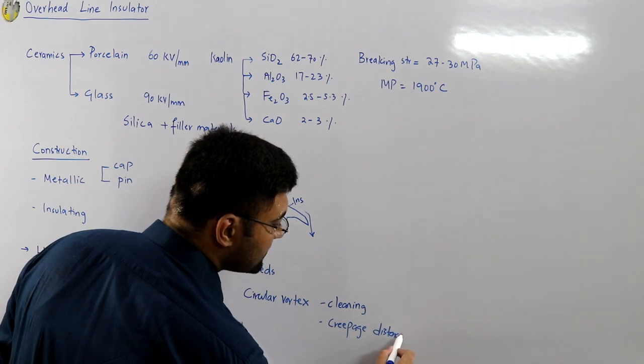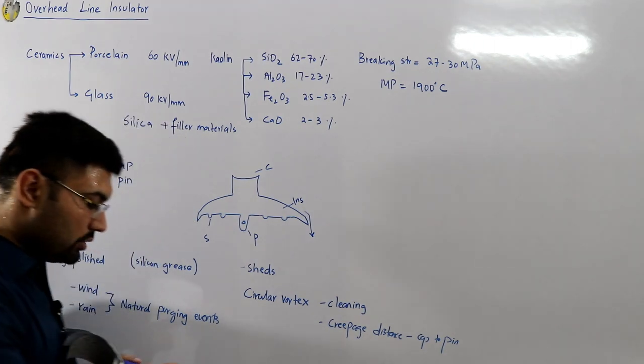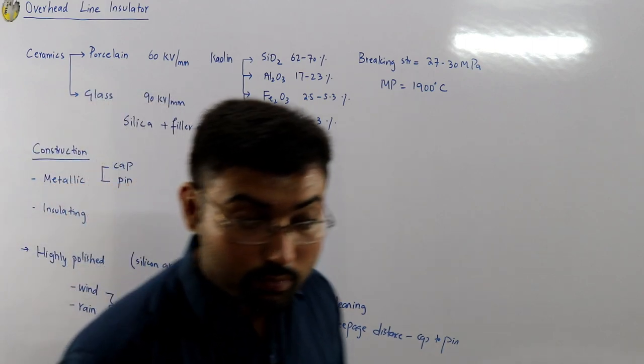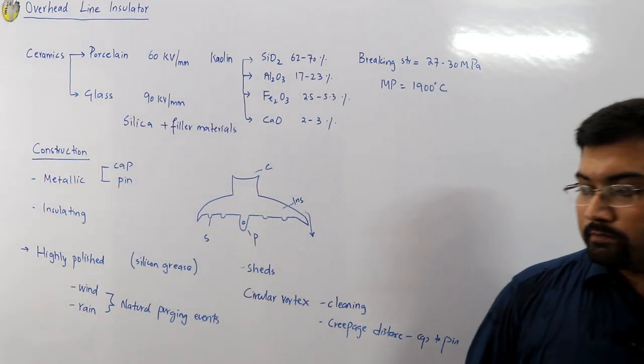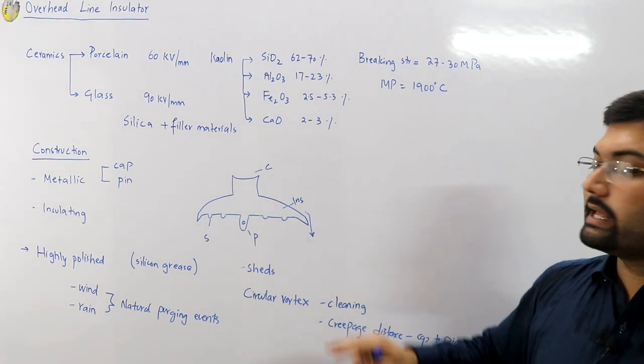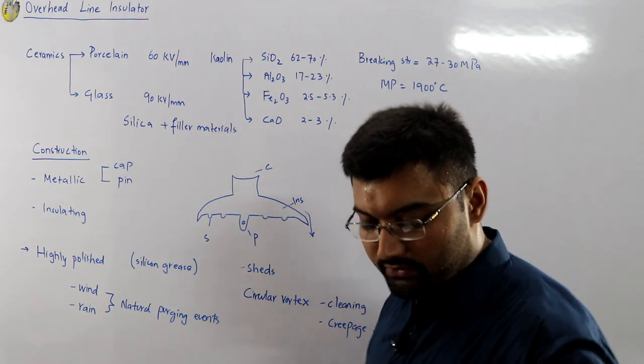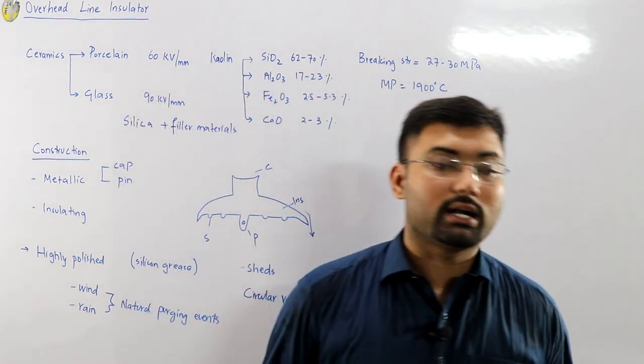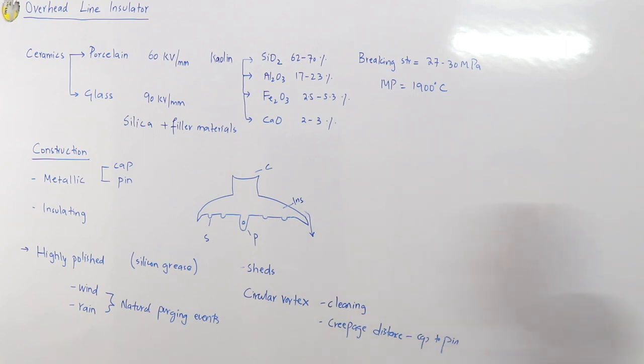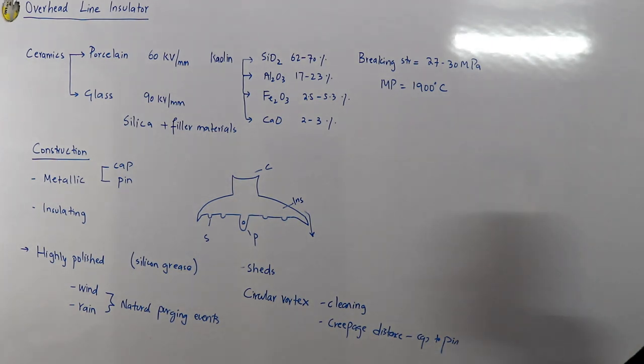The second benefit of these sheds is that they increase the creepage distance — the distance from cap to pin. Since the pin is at high voltage and the cap is at ground potential, there is leakage current. By increasing the creepage distance, you increase surface resistance, thereby reducing leakage current.